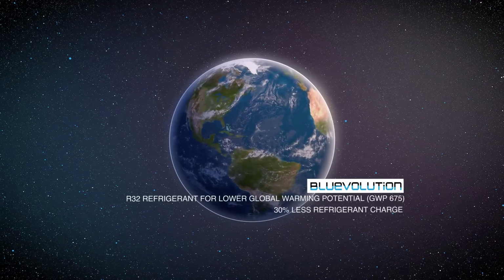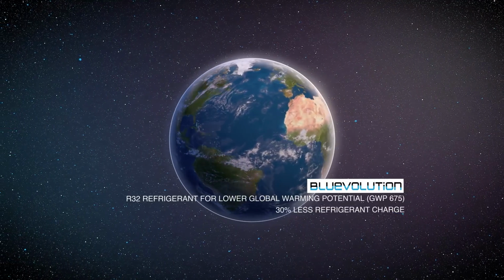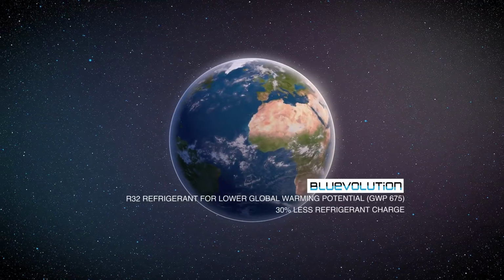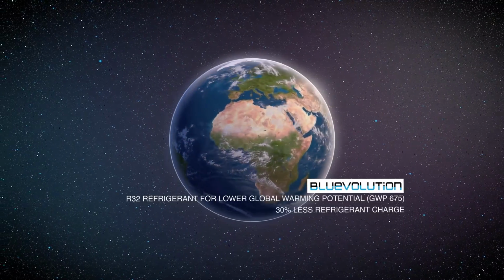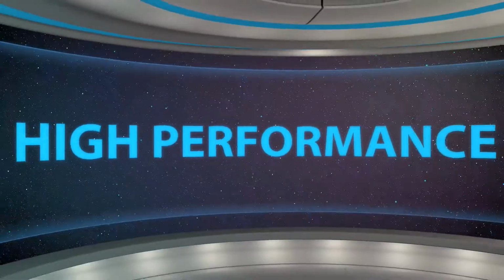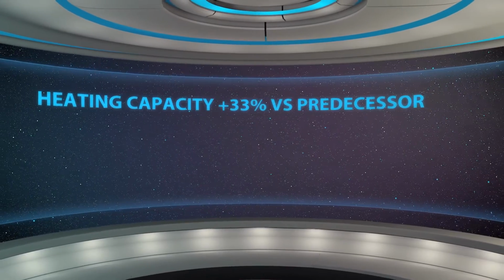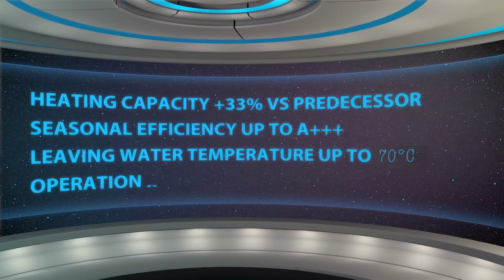One of the major reasons for the system's high efficiencies is because it uses R32 refrigerant, which has a low global warming potential and much better performance compared with any R410A based heat pump. As a result, it provides high efficiencies with a coefficient of performance or COP of 5 at 7 degrees outdoor temperature and 35 degrees leaving water temperature. And it gives a seasonal efficiencies of up to A+++.